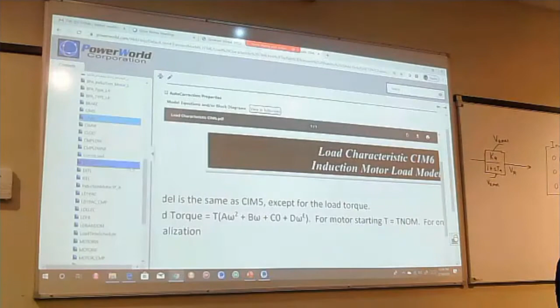The contactor model is just a model that says as the voltage drops, this is the percentage of motors that will continue to operate. There will be a point at which the voltage has gone low enough that they start tripping, and they'll go down until eventually they reach zero at some other voltage. Ideally you'd test 1 million air conditioners, but that costs too much, so they probably tested 50 instead to come up with what this looks like.